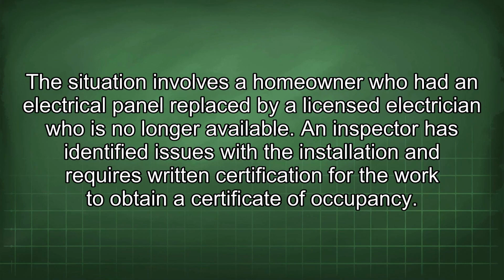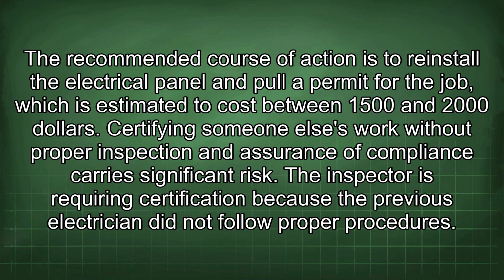The situation involves a homeowner who had an electrical panel replaced by a licensed electrician who is no longer available. An inspector has identified issues with the installation and requires written certification for the work to obtain a certificate of occupancy. The recommended course of action is to reinstall the electrical panel and pull a permit for the job, which is estimated to cost between $1,500 and $2,000.